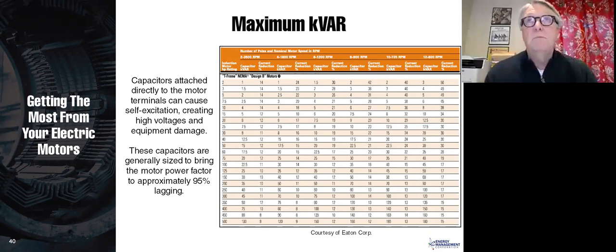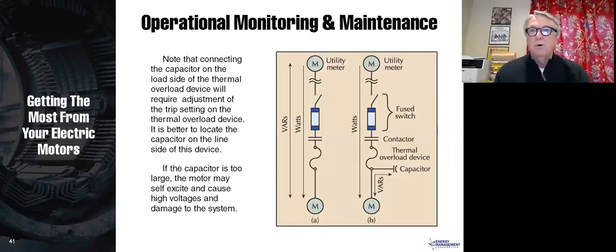By the way, we should mention never ever put capacitors on a motor if that motor has a variable frequency drive or a soft start on it, because you will instantly destroy the soft start. I'm talking about a solid state soft start, like a reduced voltage soft start with SCRs in them. I'm not talking about the mechanical starts like an auto transformer. Those are okay with capacitors, but they should basically just be on across-the-line motors for the most part.